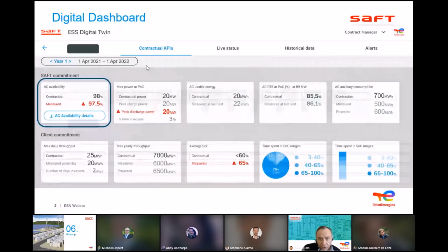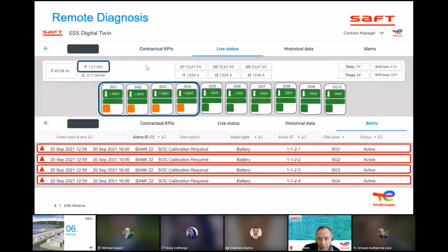In diagnosing the issue, the monitoring system flagged 4 out of 10 battery systems installed at the site with a state of charge calibration required alert. The live status screens identified the affected battery systems at the site with SOC variance across the minimum and max of about 50%. Further data analysis at each bank level identified that 2 out of 9 battery strings had an SOC variance confirming the calibration alert.